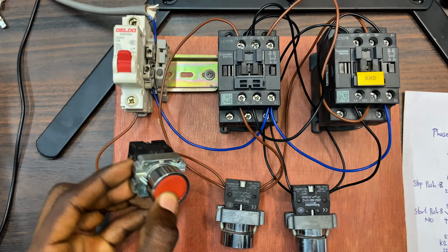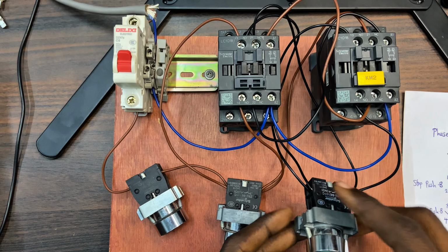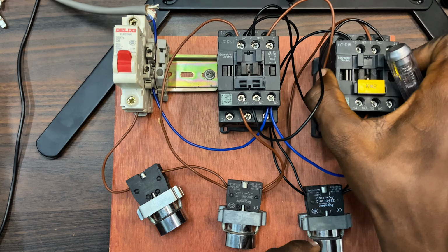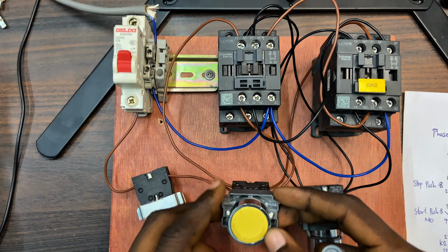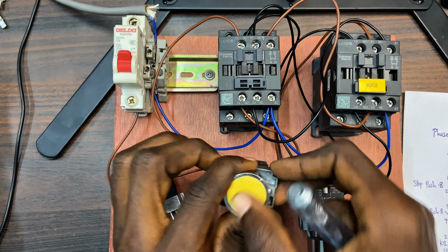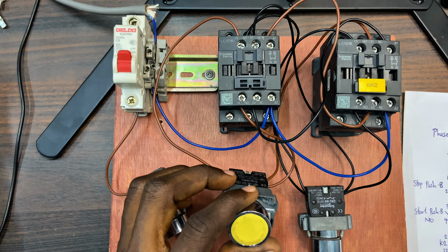Let me stop it and then push the reverse push button. So right now this contactor is working, and at the same time when I push the forward contactor push button, it is not going to work. And as I explained, this is the forward contactor. Now before this switch wire is being connected to A1, it's supposed to pass through the normally close contact we have on the contactor 2, that's the reverse contactor. The switch wire coming to the A1 is being connected to normally close contacts we have on the reverse contactor before coming to A1. As simple as that.